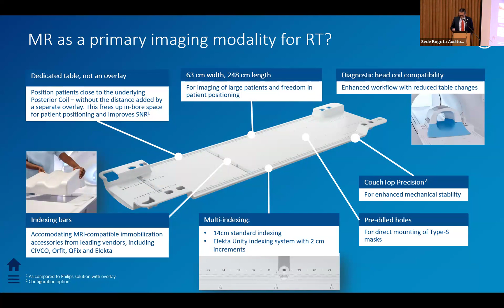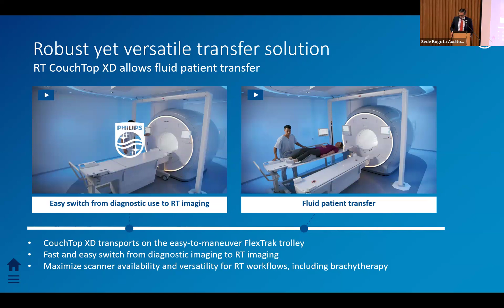And the other important thing is that in some cases it is important to move the patient from the MR table to the therapy area. And why not have an MR for routine, for instance, in the radiology area. And in the radiology area, we don't use a flat table. We use a standard table. And with this kind of method, it's possible to combine the two tables. And this kind of solution reduces the cost of a dedicated MR system.